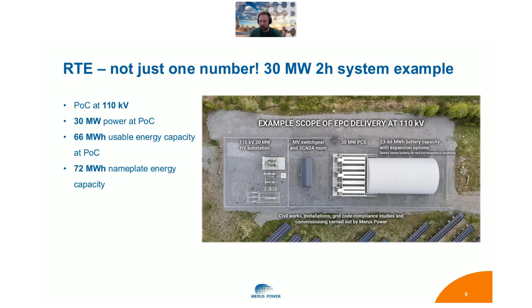Here's an example system of a 110 kV connected energy storage system. Don't be fooled by this shelter building on the right side. This could be battery containers that I'm sure many are used to seeing. This is made for Finnish very low temperature conditions originally. So in this powertrain, there's a 110 kV substation, medium voltage switchgear, power conversion system, and batteries. Here the design values are 30 megawatts of charge and discharge power at the point of connection, and then 66 megawatt hours of usable energy capacity here at 110 kV.